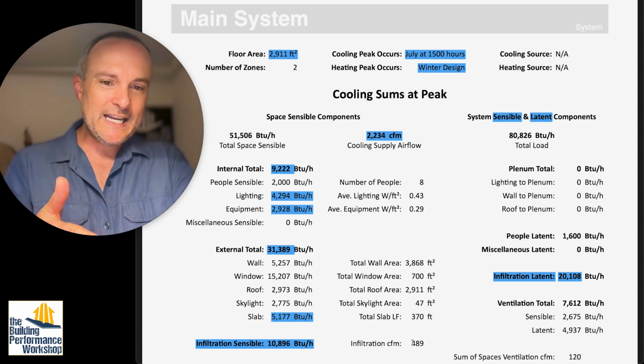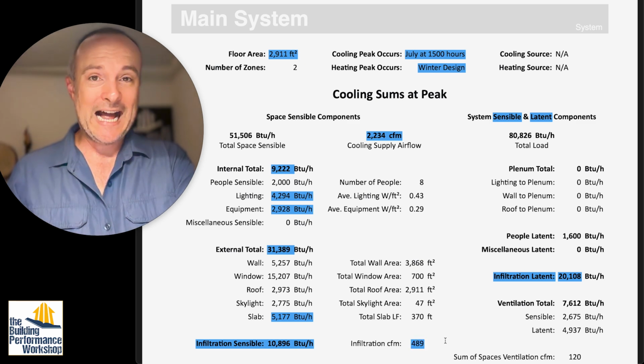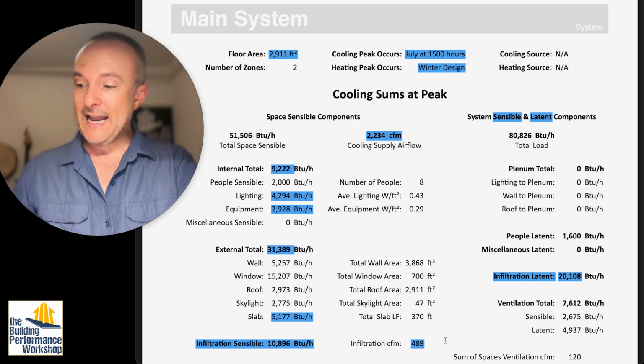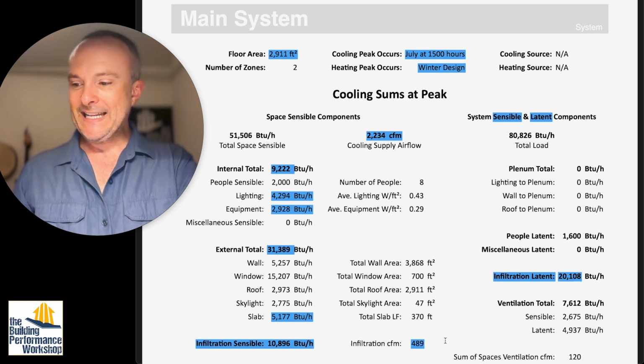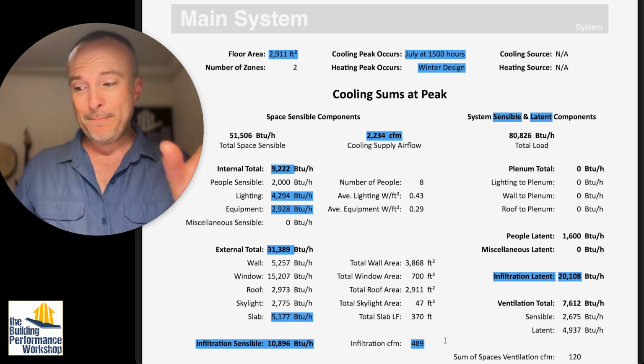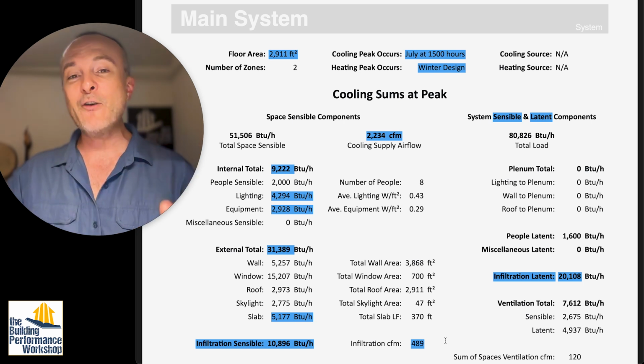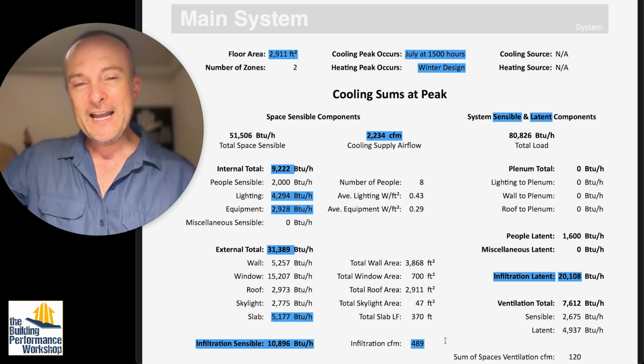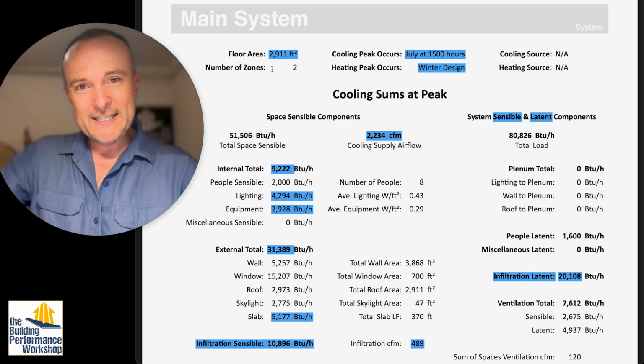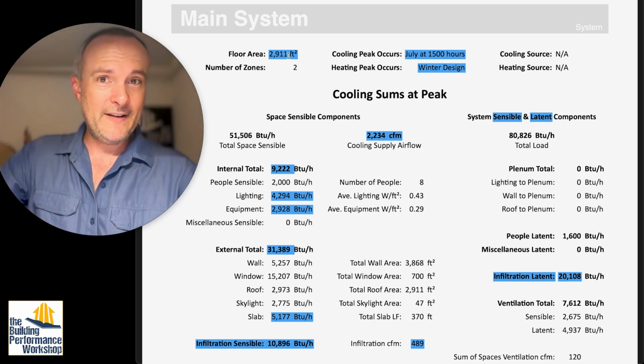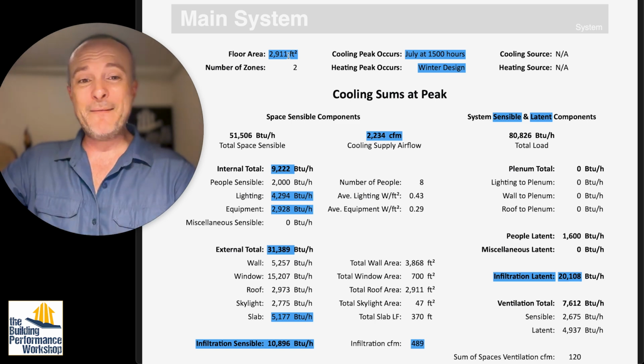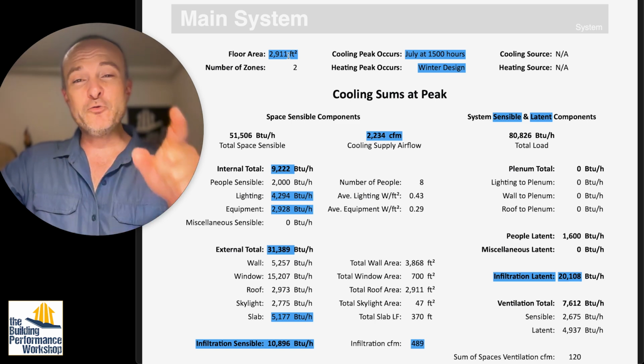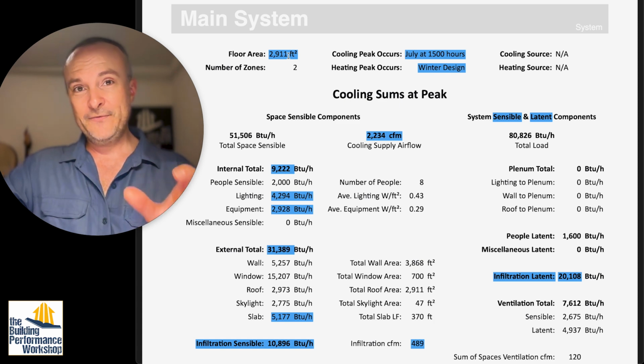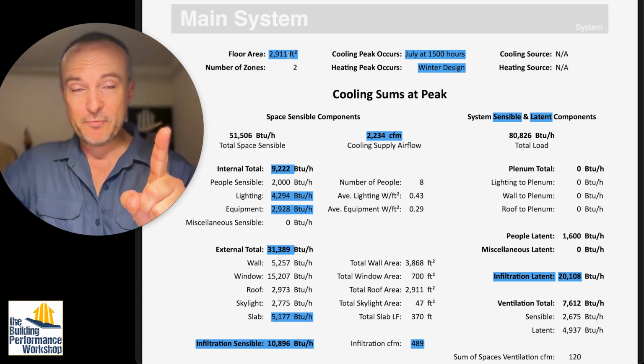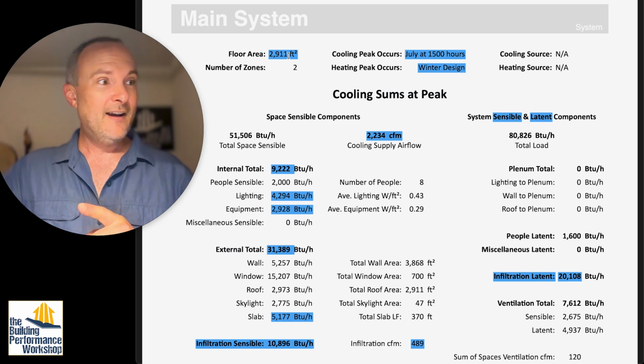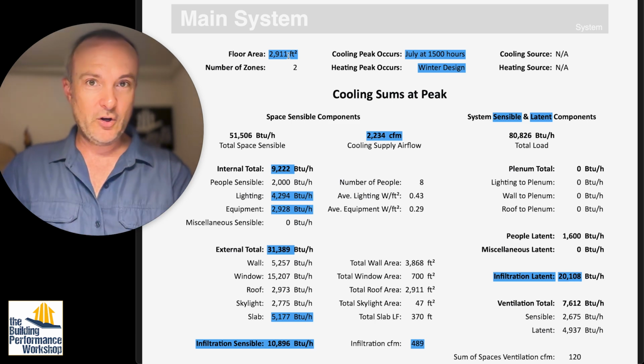So the infiltration CFM that they're imagining here is 489 CFM every minute. 489 CFM, that's cubic feet per minute, times 60 is 29,000 cubic feet per hour. If we have 10-foot ceilings in this place, 2911 square feet times 10-foot ceilings is 29,000. That means that the infiltration in here is replacing all of the air geometrically in this home once per hour, 24 times a day. Again, this is totally fake.